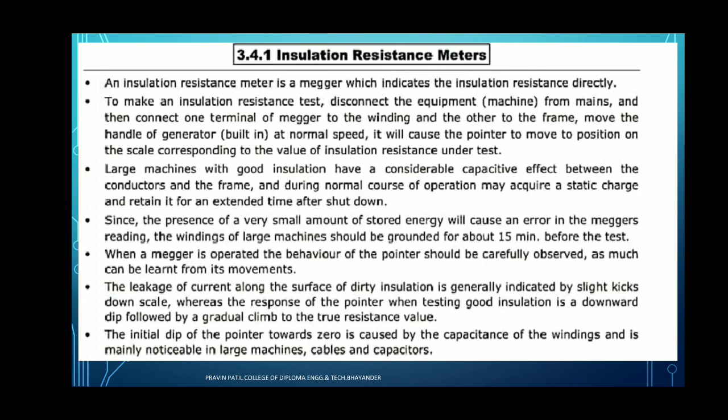Then it will cause the pointer to move to the position on the scale corresponding to the value of the insulation resistance under test. Large machines with good insulation have considerable capacitive effects between the conductor and the frame, and during normal operation may acquire a static charge and retain it for an extended time after shutdown of the electrical machine.